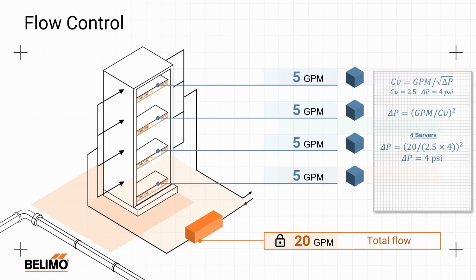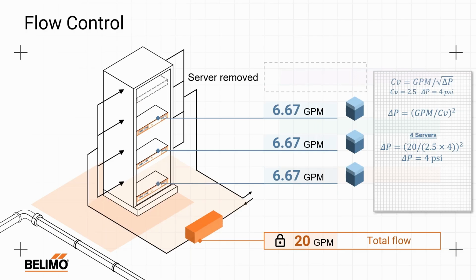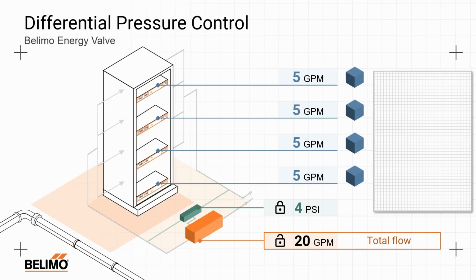The problem becomes when I remove that server, we redo the math here, we redistribute all of those things, and now the pressure drop tells me that I'm getting almost over 7 psi going across each one of these servers, where they're designed in this case for 5 psi. So we've overpressurized the servers, causing an overflow. I think this part wasn't confusing to everybody. Let's now put the differential pressure control into place and talk about how that worked, and we'll accompany it again with a little bit of math.